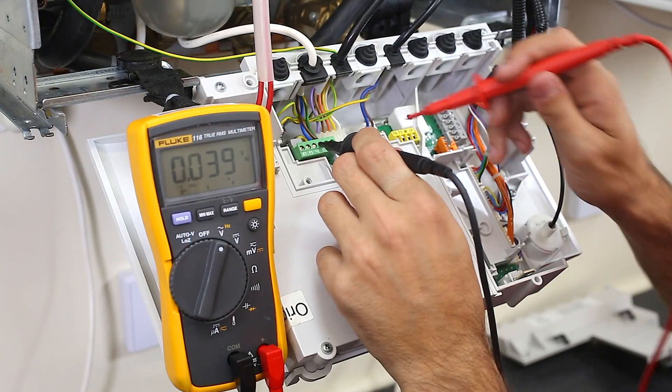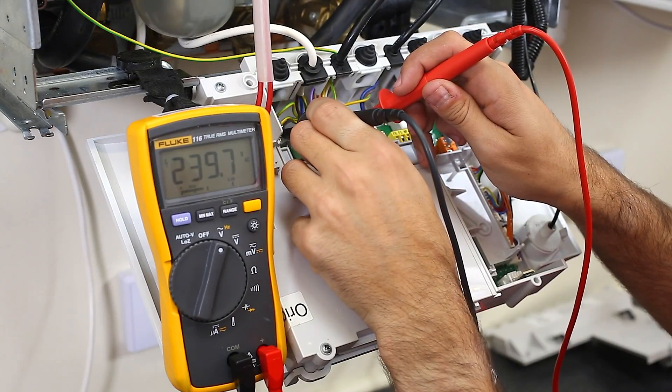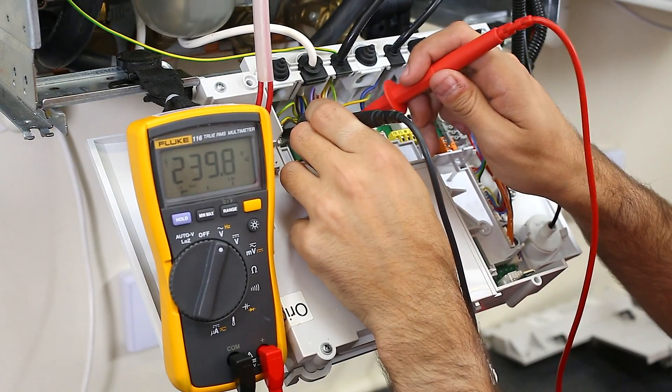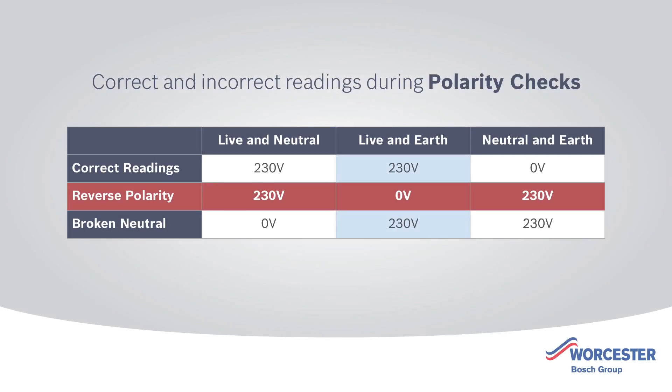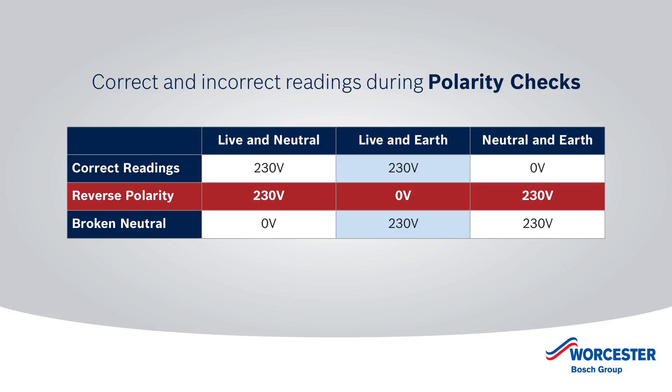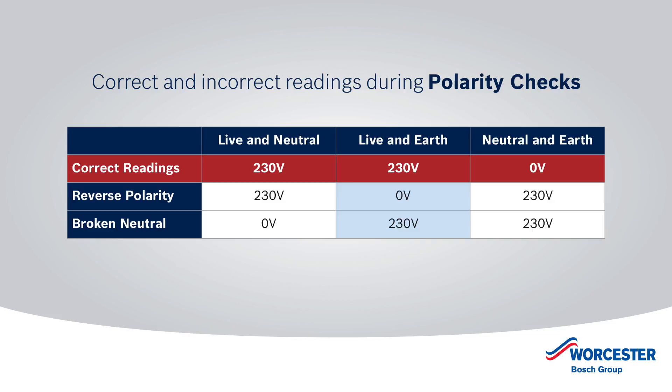The correct readings are live and neutral 230 volts, between live and earth 230 volts, and between neutral and earth 0 volts. If you have a broken neutral, you will measure 0 volts between live and earth. The nominal voltage supply is 230 volts AC, but can have a tolerance of plus 10% or minus 6%. If you do have reverse polarity or a broken neutral, identify and rectify the faults so the correct voltage and polarity readings are achieved.